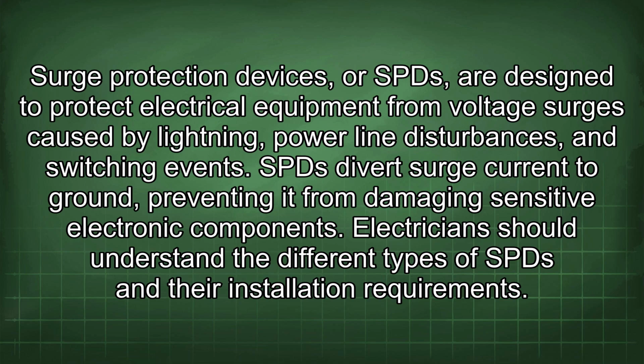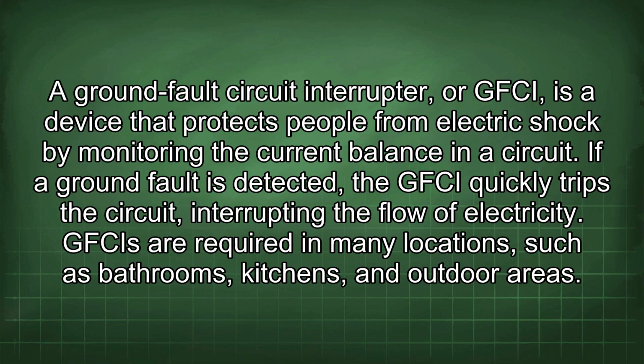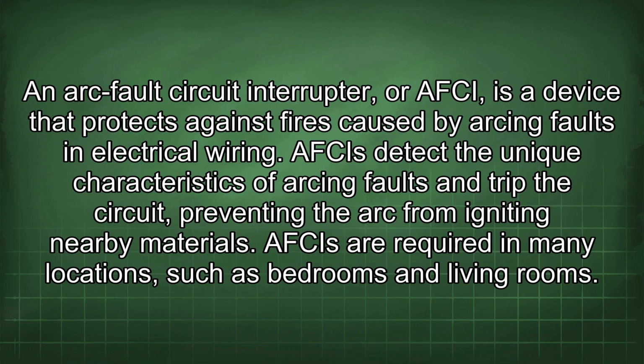installation requirements. A ground fault circuit interrupter, or GFCI, is a device that protects people from electric shock by monitoring the current balance in a circuit. If a ground fault is detected, the GFCI quickly trips the circuit, interrupting the flow of electricity. GFCIs are required in many locations, such as bathrooms, kitchens, and outdoor areas. An arc fault circuit interrupter, or AFCI, is a device that protects against fires caused by arcing faults in electrical wiring. AFCIs detect the unique characteristics of arcing faults and trip the circuit, preventing the arc from igniting nearby materials. AFCIs are required in many locations, such as bedrooms and living rooms.